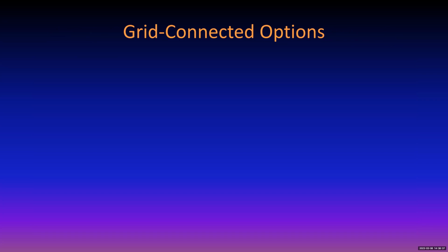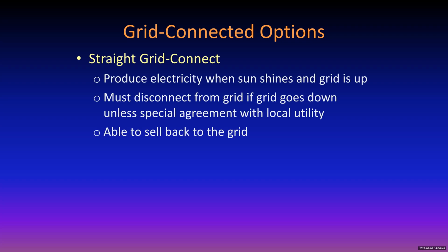All right, so let's look at grid connected systems. We are going to talk only about grid connected systems, and we're going to talk about grid connected systems without batteries. All right, there's a straight grid connect, and it makes electricity when the sun shines and the grid is in operation. But if the grid goes down, the system has to disconnect, because after all, you don't want your electricity powering up those power lines. Some maintenance guy is up near the distribution line trying to repair it, and all of a sudden your PV system, through the transformer, puts out 12,000 volts that was not expected, and it's not very welcome. So therefore, it has to disconnect from the grid if the grid goes down.